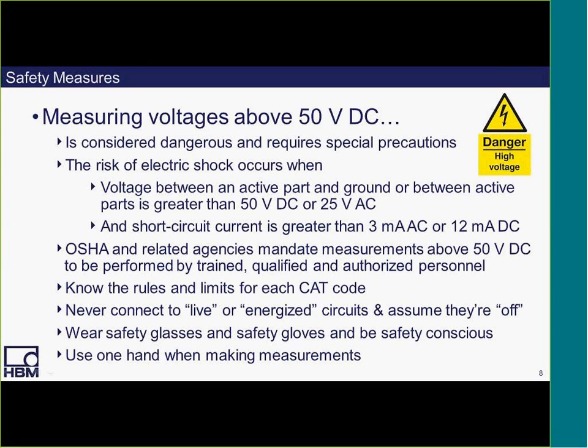So we'll begin with the most important concern, and that is safety. Some or most of this may seem obvious, but it's important enough to remind ourselves to be safety conscious and be aware of the danger involved. Measuring voltages above 50 volts DC is considered dangerous and requires special precautions. The risk of electric shock occurs when voltage between an active part and ground, or between active parts, is greater than 50 volts DC or 25 volts AC, and short circuit current is greater than 3 milliamps AC or 12 milliamps DC.